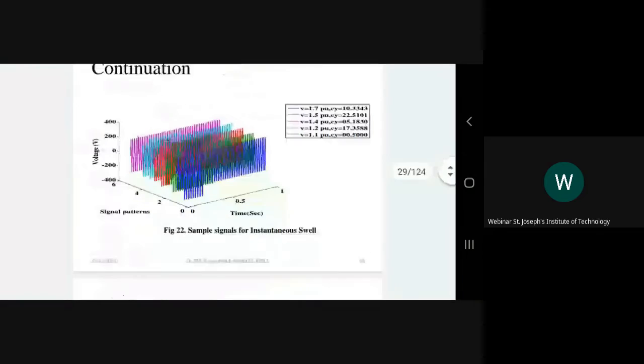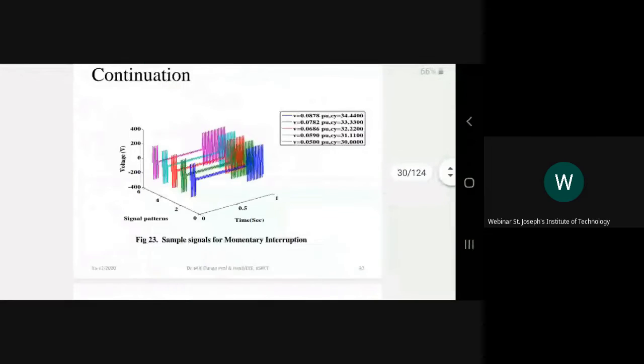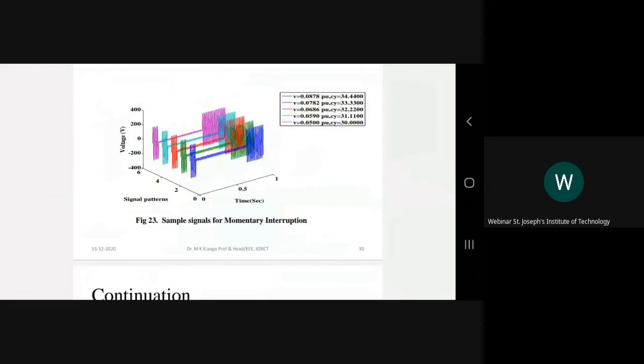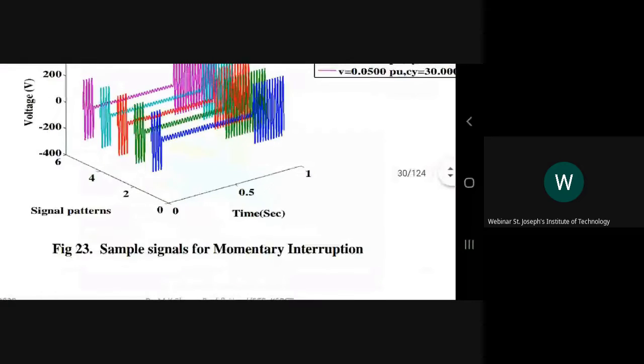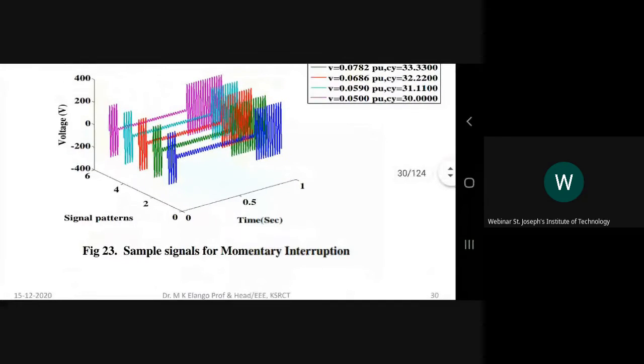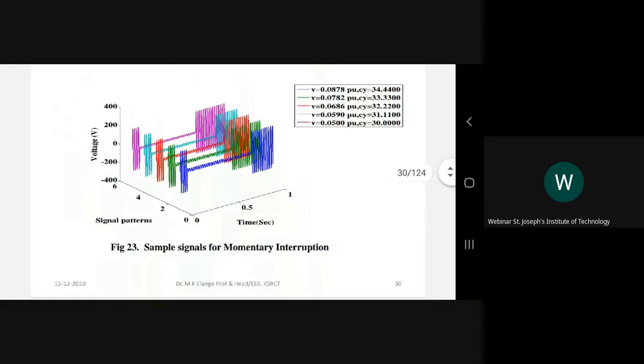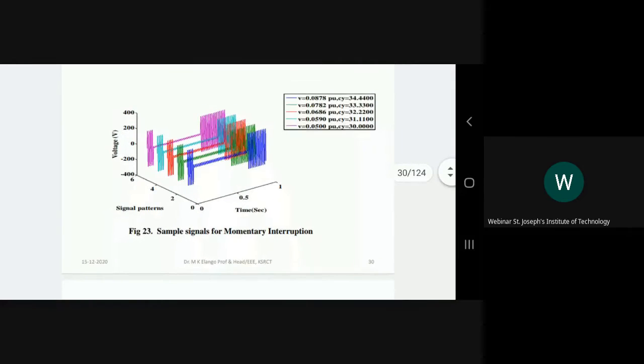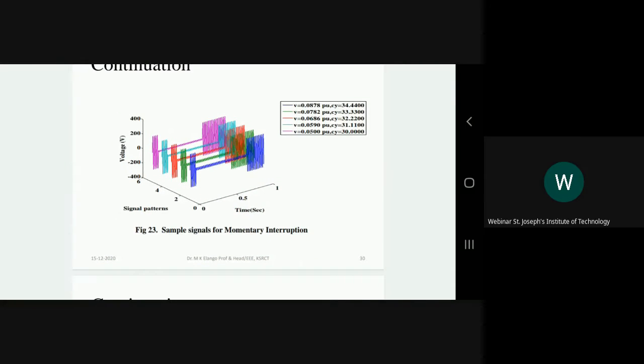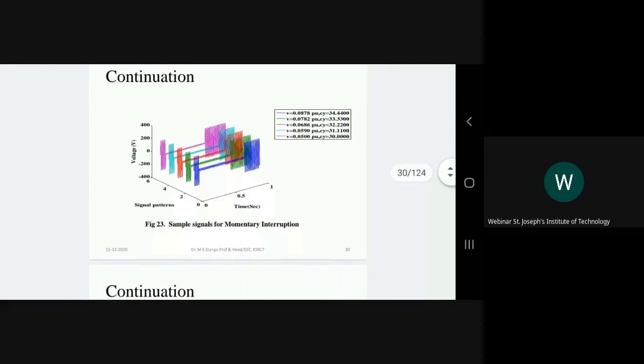As per the IEC standard, I have created the real-time database for instantaneous sag, and similarly for instantaneous swell. This is the waveform for momentary interruption. For momentary, the time duration is much longer, 30 cycles to 3 minutes, so the waveform I have taken is 1 second, showing how many cycles vary within that second. This is the waveform for momentary interruption, and this is the waveform for momentary sag.